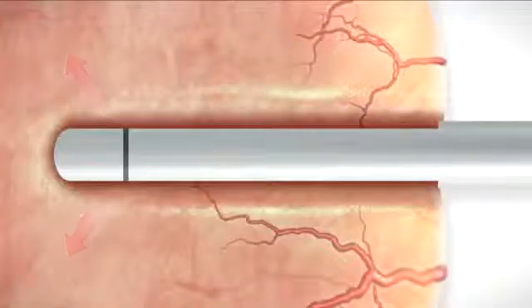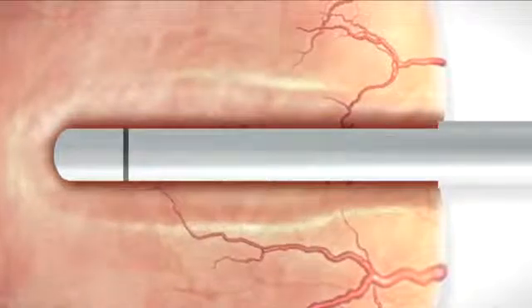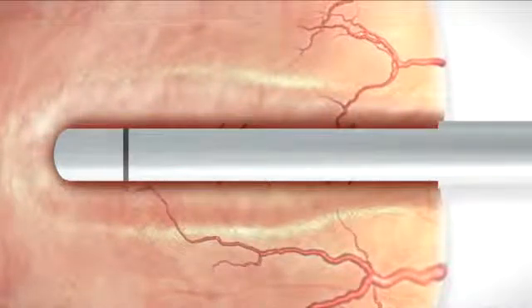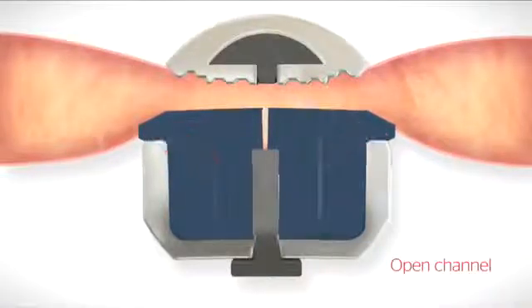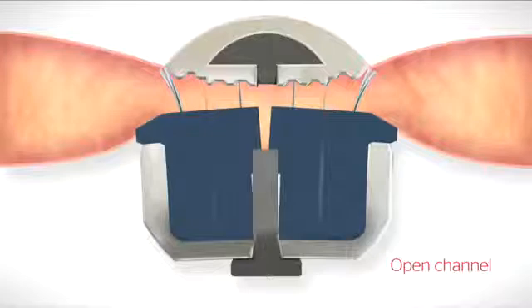Tissue slippage occurs both longitudinally and laterally. Tissue flow and the high forces in thicker tissue firings can cause stress and bowing in an open channel gun, which can result in deck deflection. This can trigger staple legs to hit the wrong anvil pockets and, in some cases, miss the anvil pockets entirely.